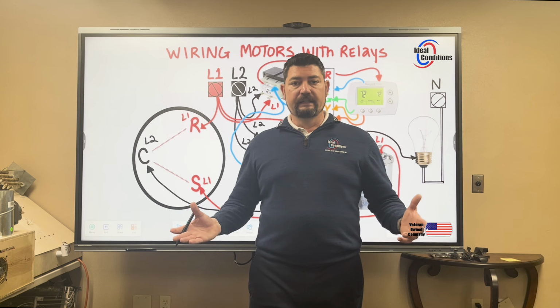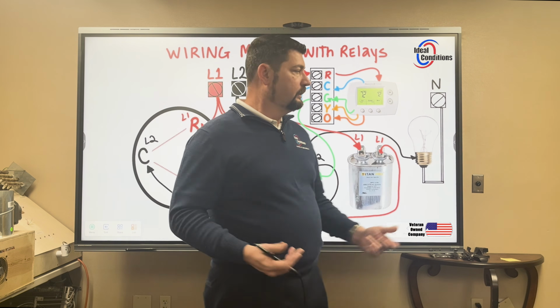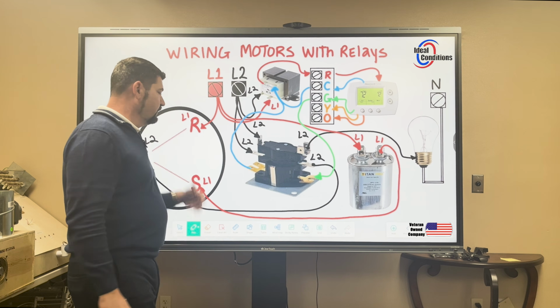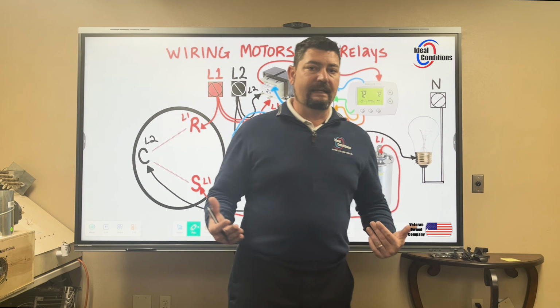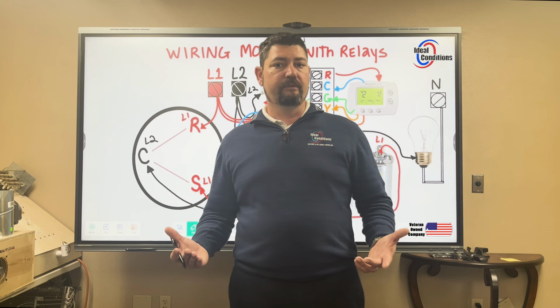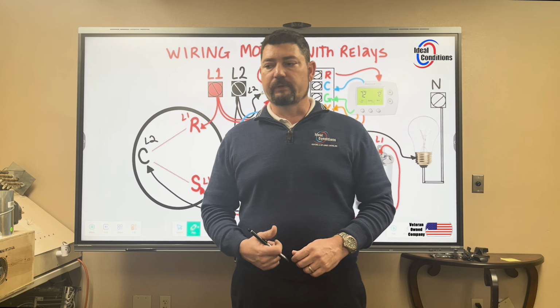Any relay that's normally open can be used for a blower motor because the ampacity is not that high. You can't use it for a compressor now, but you can definitely use it for a blower motor.